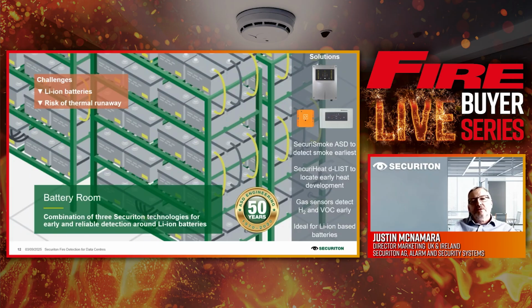At Securiton, we're able to address that with a combination of aspirating smoke detection, similar to what we've seen within the server room itself, but also with some gas sensors, either hydrogen or VOC (volatile organic compound) sensors, that we can incorporate into our design to provide very early detection of battery failure in lithium-ion batteries.